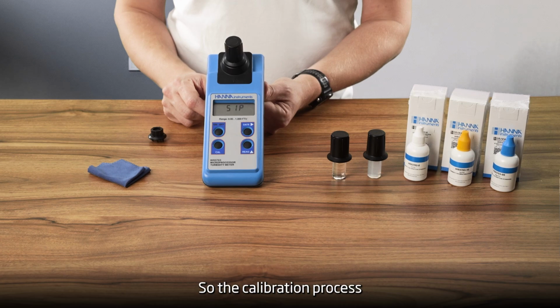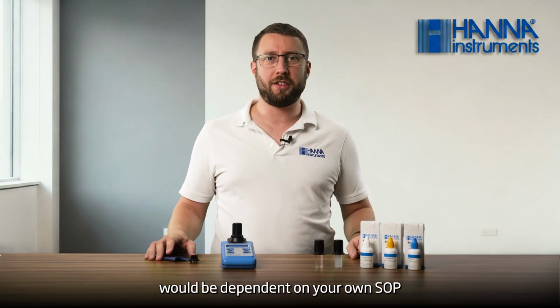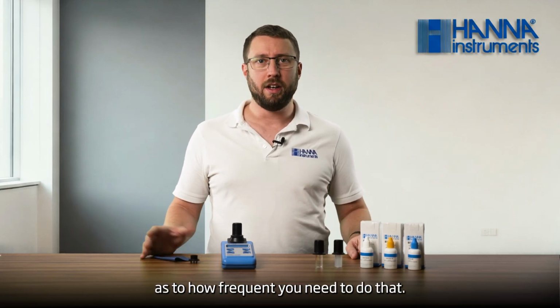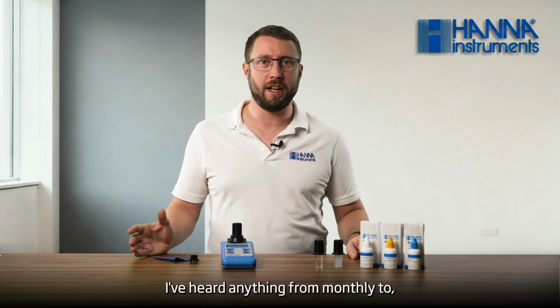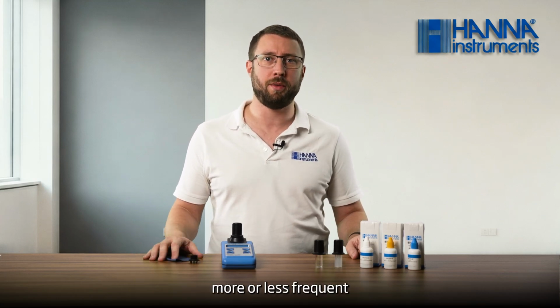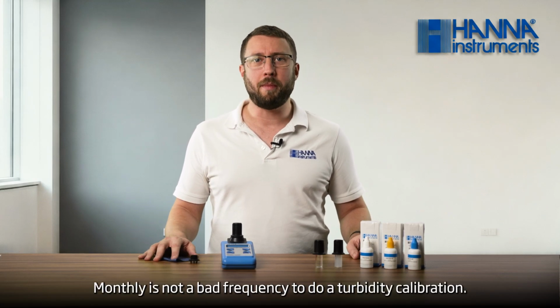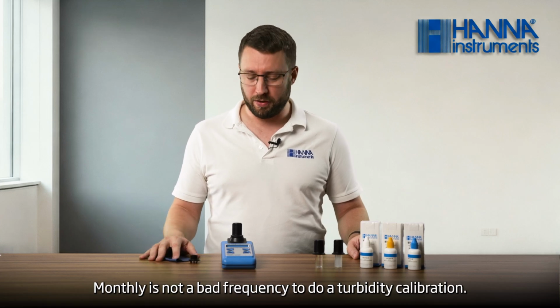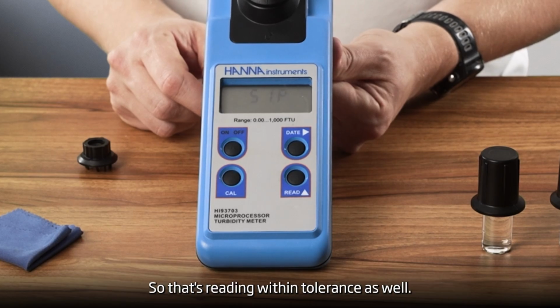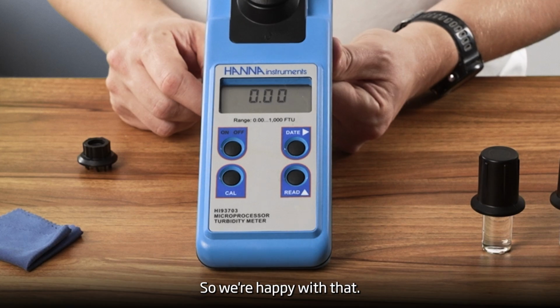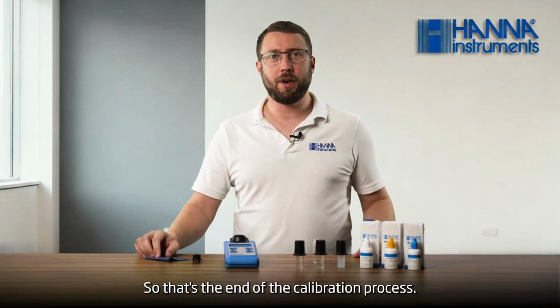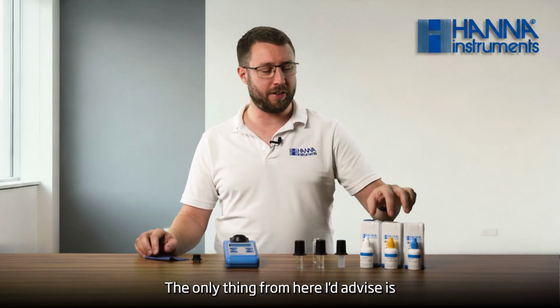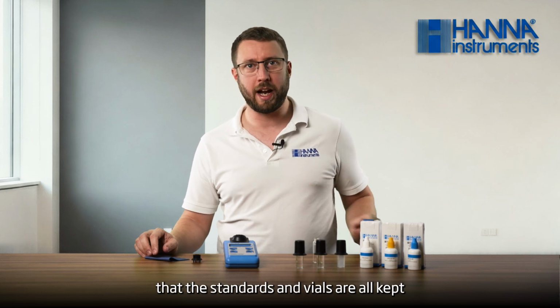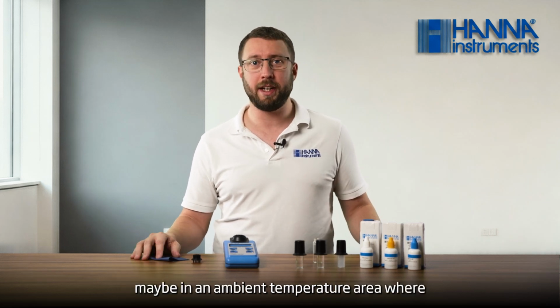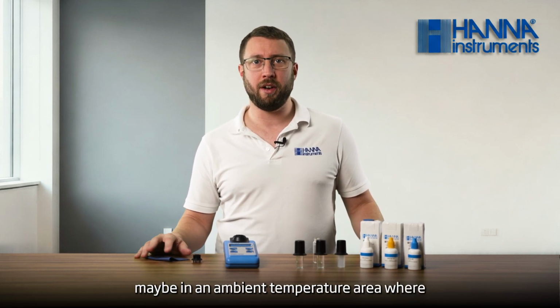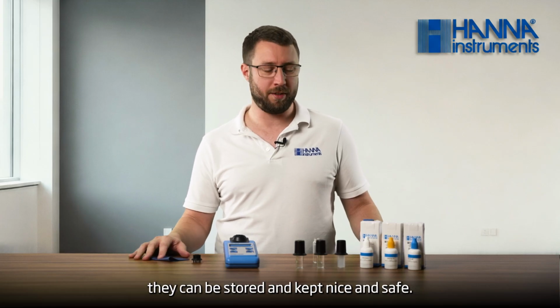So the calibration process would be dependent on your own SOP as to how frequent you need to do that. I've heard anything from monthly to, more or less frequent than that. Monthly is not a bad frequency to do a turbidity calibration. So that's reading within tolerance as well, so we're happy with that. So that's the end of the calibration process. The only thing from here I'd advise is that the standards and vials are all kept safe, in a cupboard maybe, in an ambient temperature area where they can be stored and kept nice and safe.